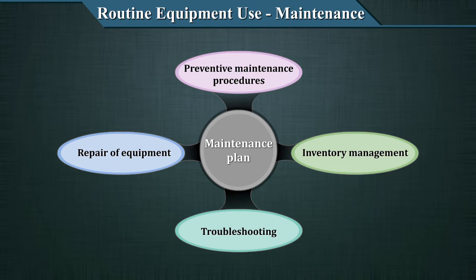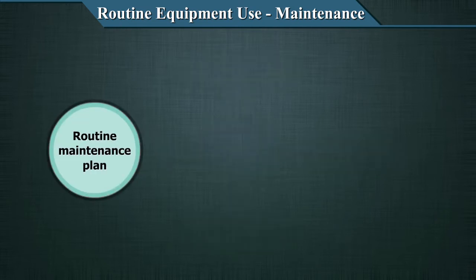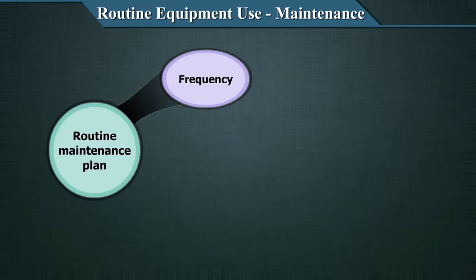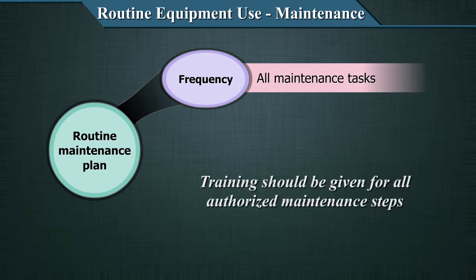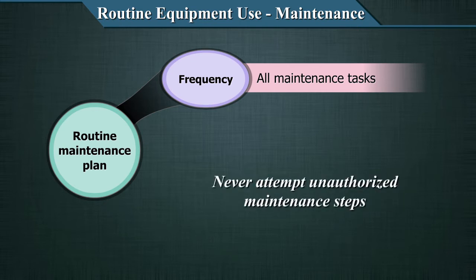For each piece of equipment, establish a routine maintenance plan to include the frequency of all maintenance tasks — daily, weekly, monthly, three-monthly, as needed, etc. Training should be given for all authorized maintenance steps. Never attempt unauthorized maintenance steps.